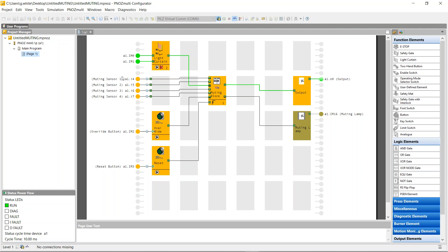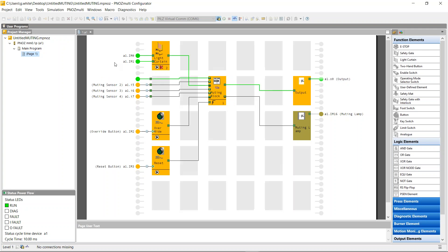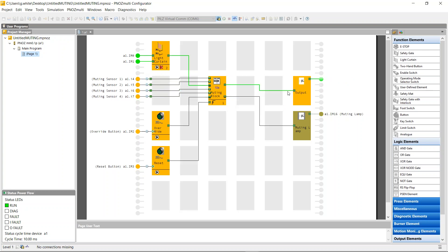So everything is good. And we'll say a pallet is traveling up through the conveyor and it's just about to hit muting sensor one. So if it hits muting sensor one, then two, then three, then four, everything's okay. And if it turns off, then one, two, three, and four, you can see that the output stayed healthy.